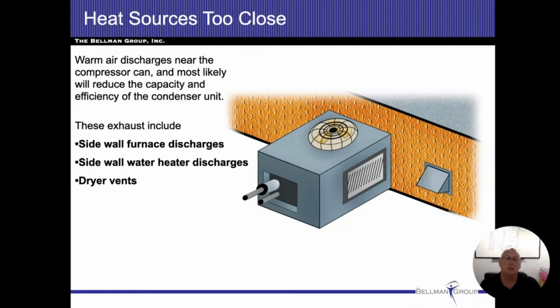Now, sidewall water heater discharges. That will operate when the air conditioning is operating. And remember, we're trying to discharge heat. So if we have hot air that's blowing on top of it, that just makes it more difficult to discharge the heat. And direct vent water heaters are also considered condensing water heaters. Condensation does come out of that as well. So yeah, I think that's going to damage it also.